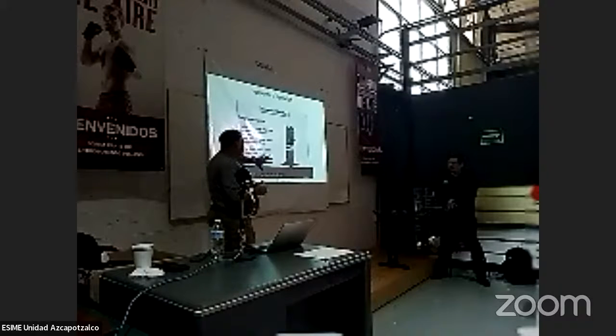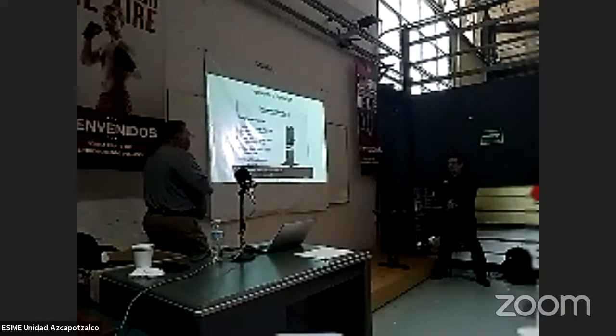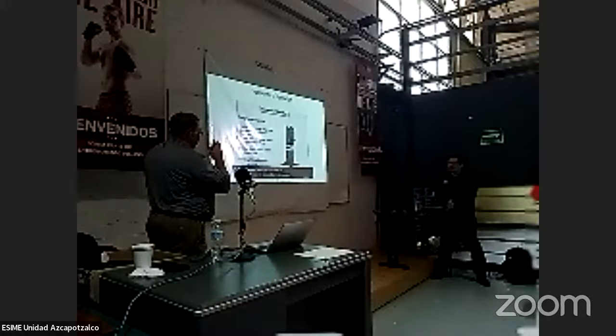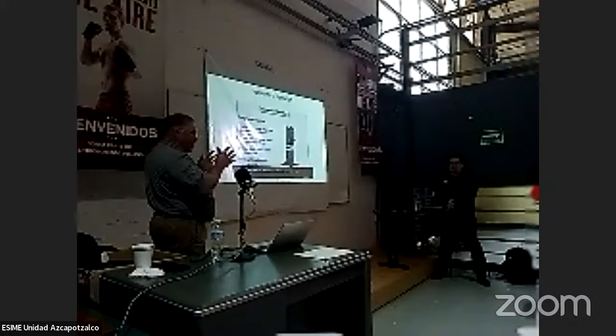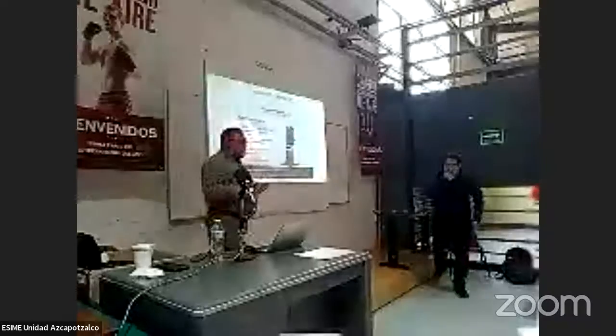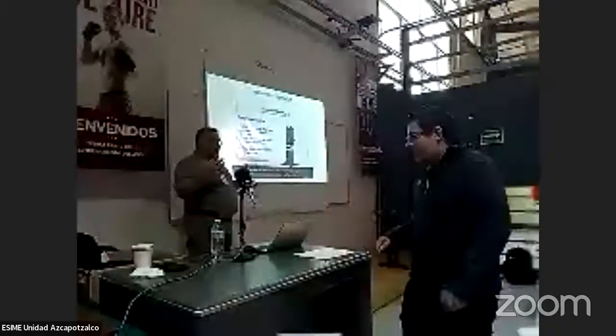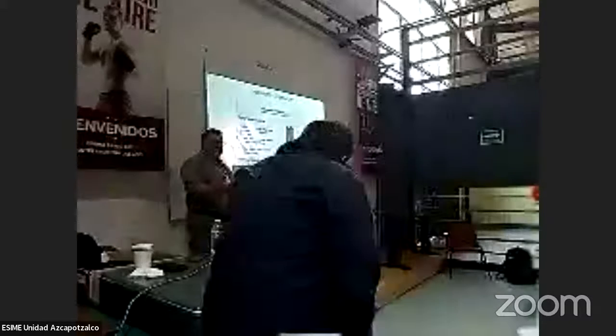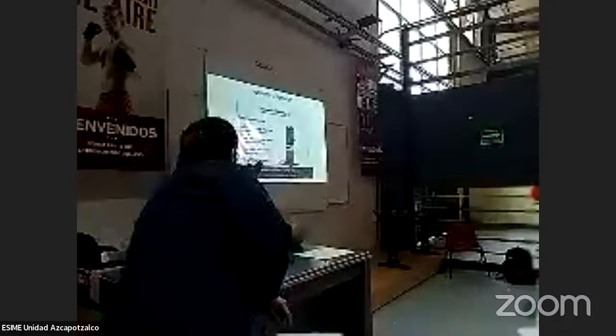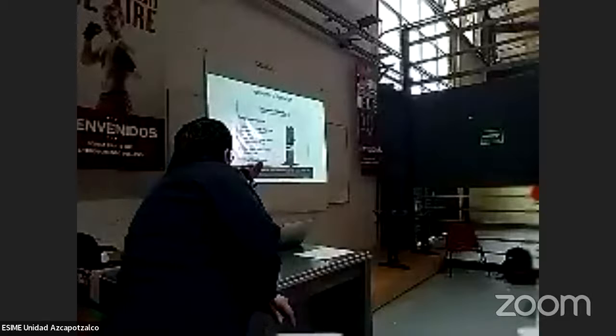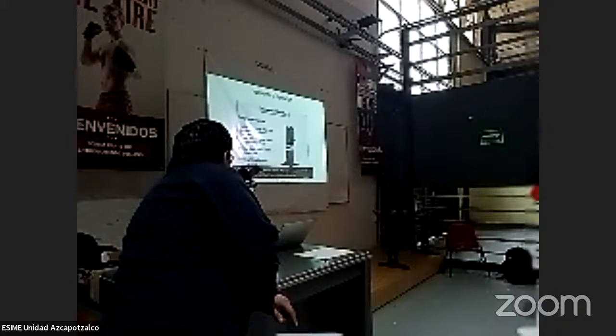Anyway, so we can carry that speed. One thing I want you to know about the actual speed we hear by model is 7,000 RPM. These systems don't sound like normal systems. These compressors, when they're at 7,000 RPM, can have a high-pitched whining sound, and that's normal operation. So if that happens, you don't have a problem. You need to see what RPM you're operating at. You can see that on the Econet thermostat. They tell you what RPM the compressor is at. Okay, so you can look at that.